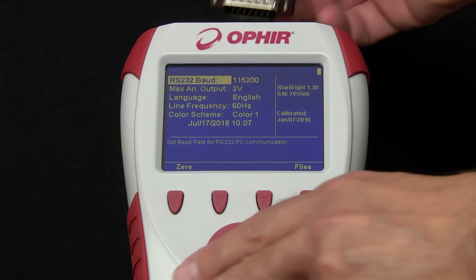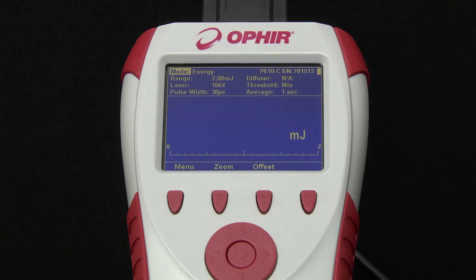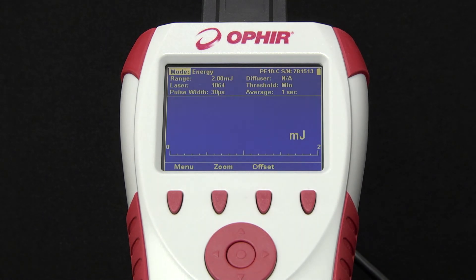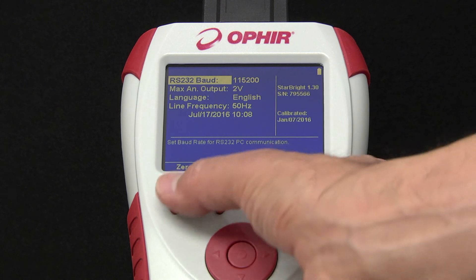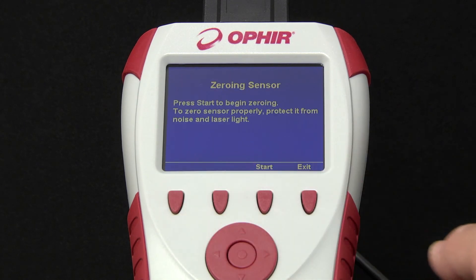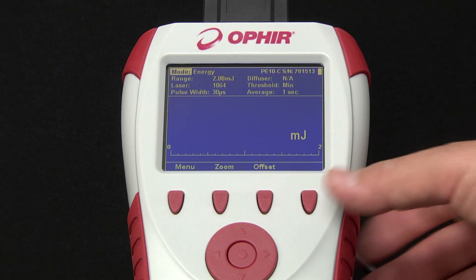We'll now connect a pyroelectric sensor used for measuring energy per pulse of a repetitively pulsed beam. Note that some energy sensors, particularly the most sensitive models, are actually based on photodiode rather than pyroelectric detectors, but the operation is the same. For the most accurate reading, we recommend performing zeroing with the meter and the specific sensor connected. Once done, you won't need to do that again for this sensor as long as it's being used with the same meter type — in this case StarBright. When you change meter types, you'll want to re-zero the sensor.